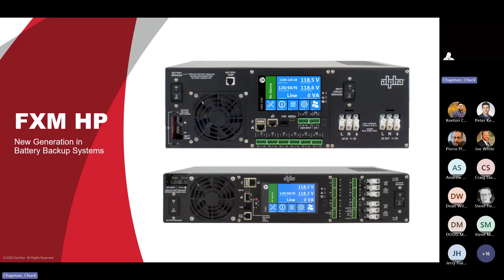With the universal automatic transfer switch, if anything happened to the inverter, the system would bypass both the input and output and put the energy directly from the source to the load. But you can also use that as a way to test the inverter - you can shut off one of the switches and the inverter will turn on, providing output to the load. If anything were to happen again during that time, the ATS would automatically shut off or take it back from line to load.